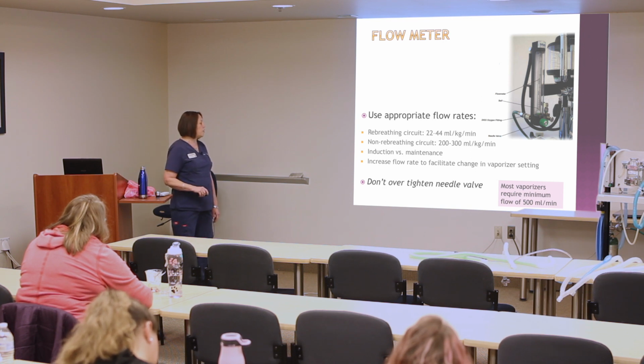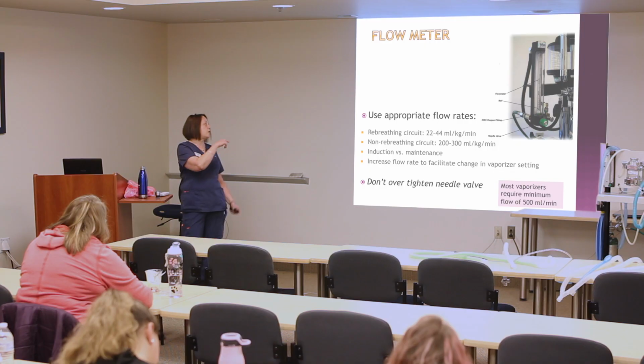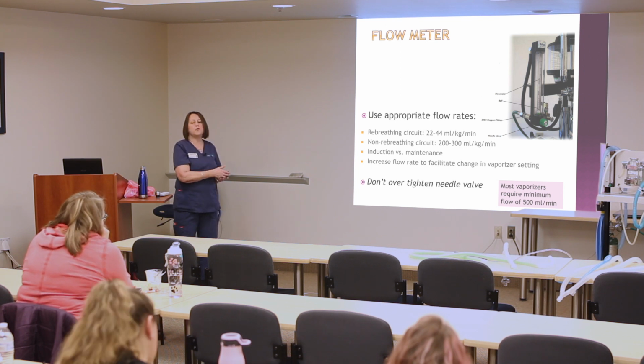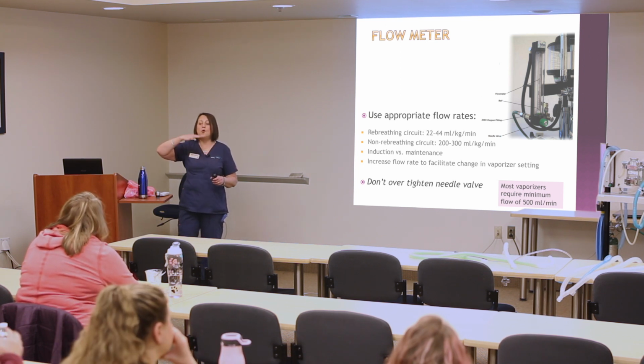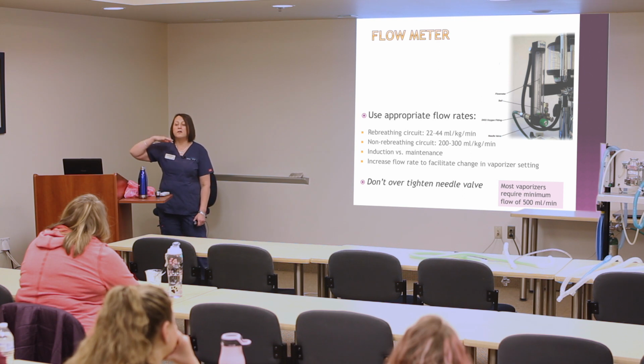You can do low flow anesthesia because we are measuring inspired and expired carbon dioxide. So when you get that little bitty guy and you're using side stream technology to measure carbon dioxide, because of sample dilution, because of the 200 to 300 mLs per kilo per minute, these high oxygen flow rates, and how much carbon dioxide is that little 12-ounce kitten going to make? Not much at all. So you might not see a lot of carbon dioxide coming out on your waveform, not the normal 25 to 35 that I would expect.